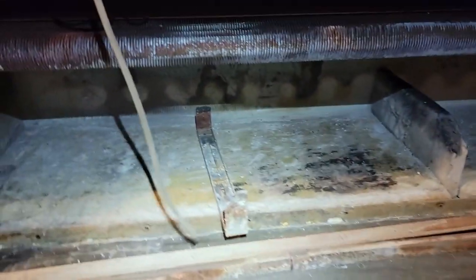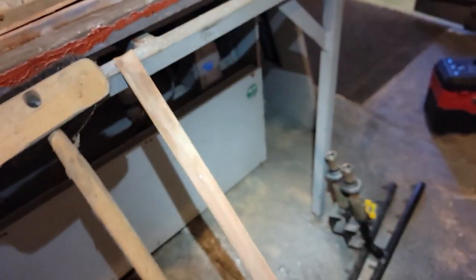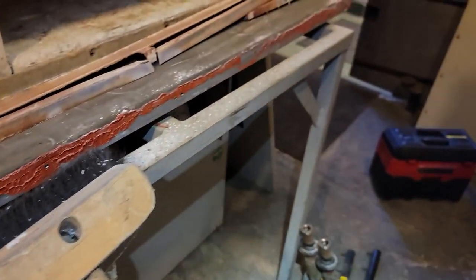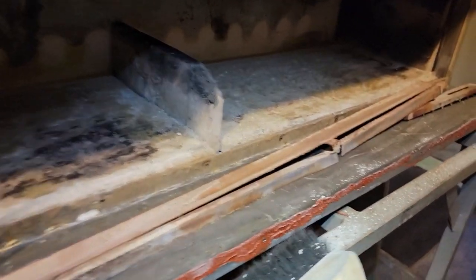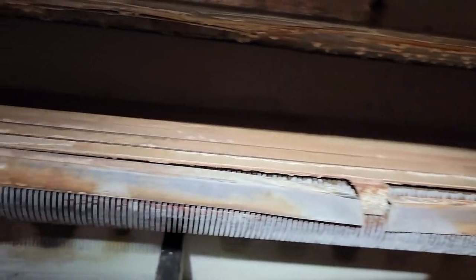These here, they're just a V-shape, and that V-shape is going down in between the tubes. You've only got a small little area that it can come through. With that little bit of gunk on it, it's going to throw it off. If you can't get your exhaust fumes out of there, you're going to have a concentration of them and your CO is going to go sky high. I can't help but wonder how long has it been like that, and did somebody adjust the gas pressure lower to make up for it possibly.